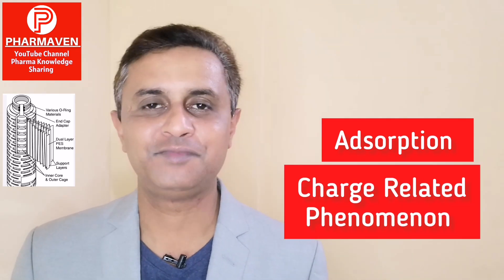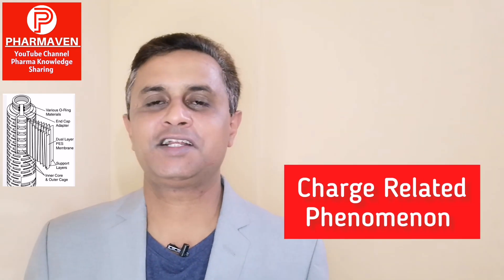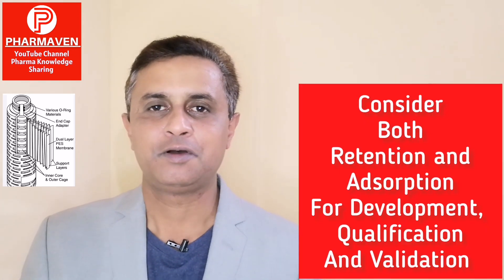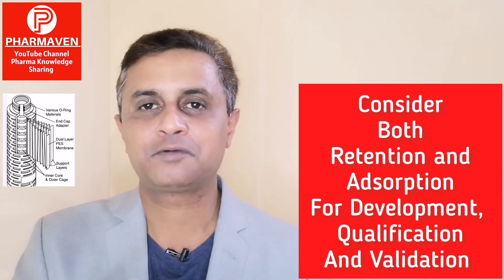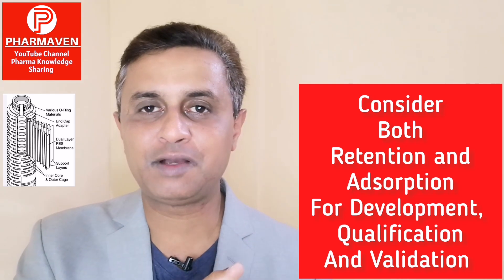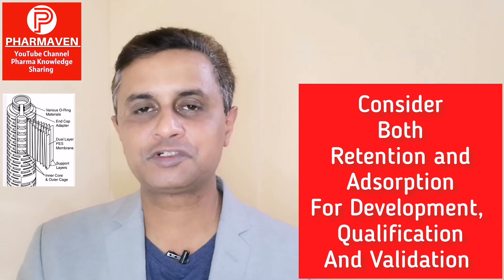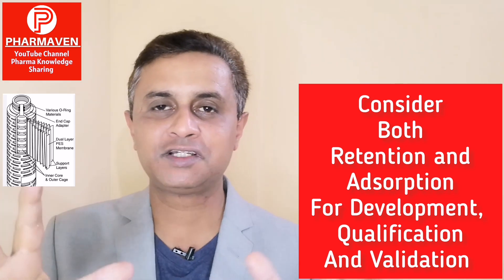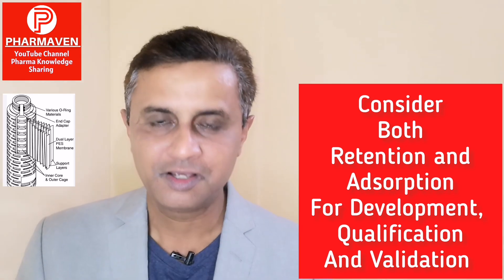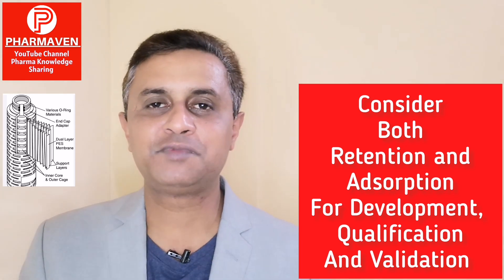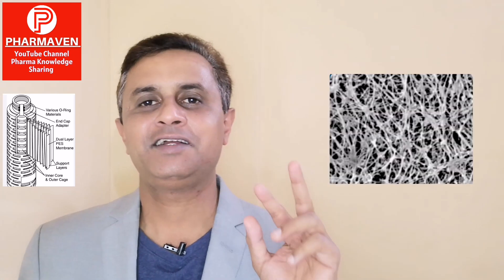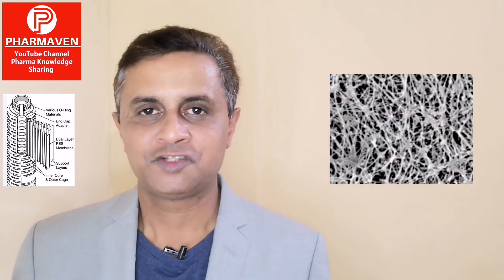For the validation of the filter — defining your membrane, determining qualification, and finally validating the filter using the product — you need to consider both mechanisms: retention by sieving and retention by adsorption. So first, let's understand retention by sieving.